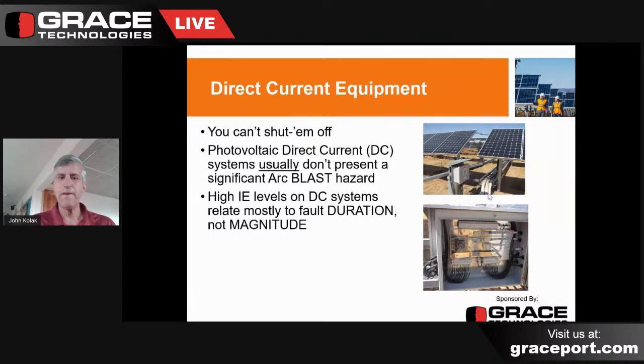Now, the next point is important. Photovoltaic direct current equipment usually, but not always, doesn't present a significant arc blast hazard. You should be aware that in the electrical regulations that relate to anything other than solar and wind farms, when we talk about arc flash hazards for clothing, it really wasn't the initial arc blast that was the problem. What was the problem is there would be a blast of such magnitude that it would knock the worker either unconscious or knock them so silly that they can't participate in their own rescue, and their clothing would start on fire. So they'd essentially be knocked out and they would die, burned to death by their own clothing.